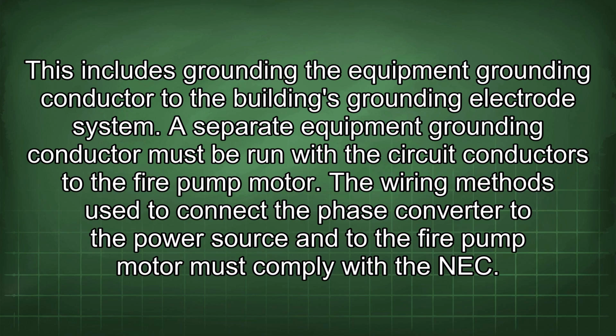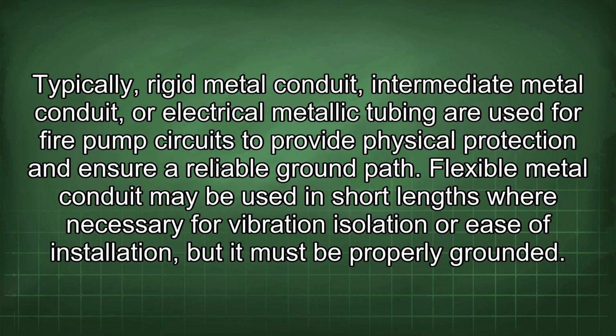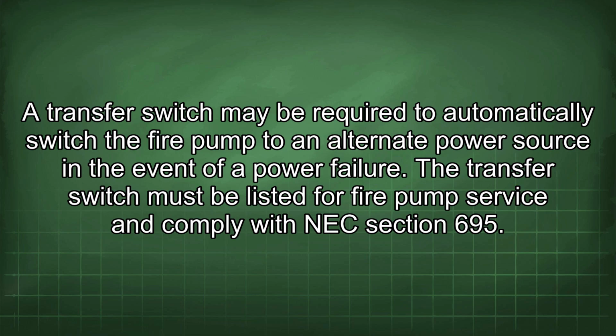The wiring methods used to connect the phase converter to the power source and to the fire pump motor must comply with the NEC. Typically, rigid metal conduit, intermediate metal conduit, or electrical metallic tubing are used for fire pump circuits to provide physical protection and ensure a reliable ground path. Flexible metal conduit may be used in short lengths where necessary for vibration isolation or ease of installation, but it must be properly grounded.